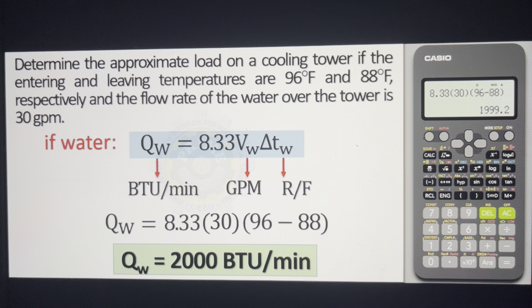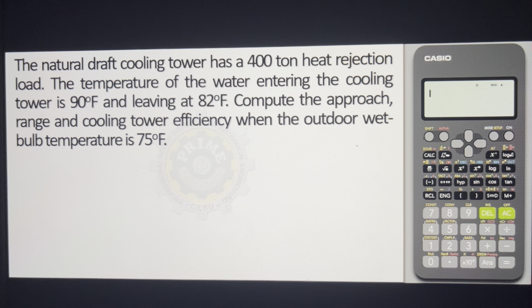Next problem. The natural draft cooling tower has 400 tons of heat rejection load — yun yung QW kanina. The temperature of the water entering the cooling tower: kung aaralan natin, 1 and 2 para sa air, 3 and 4 para sa water. Entering ng water is 3, that is 90, and leaving ng water is 4, that is 82. Compute the approach and the range of the cooling tower and also the efficiency when the outdoor wet bulb temperature is 75, TW1 = 75. Kunin daw yung tatlo: range, approach, efficiency ng cooling tower.